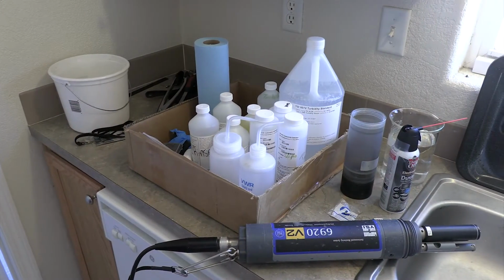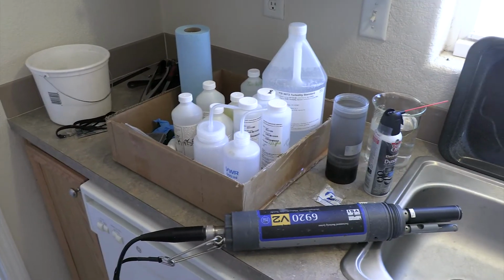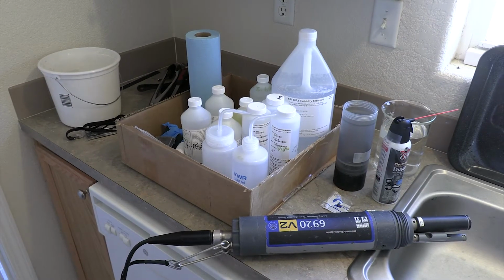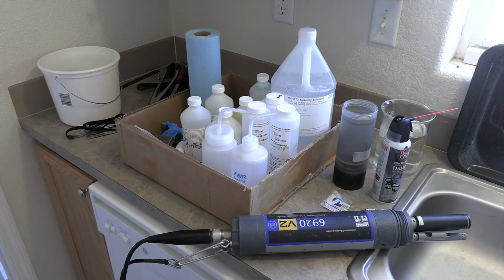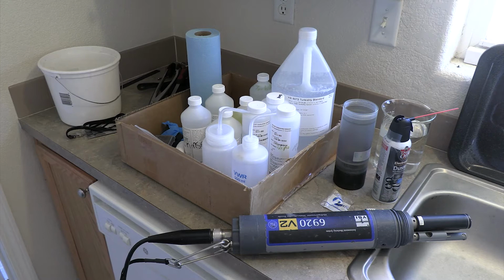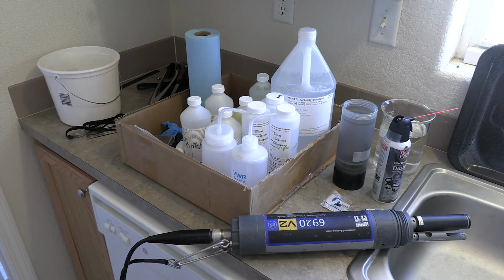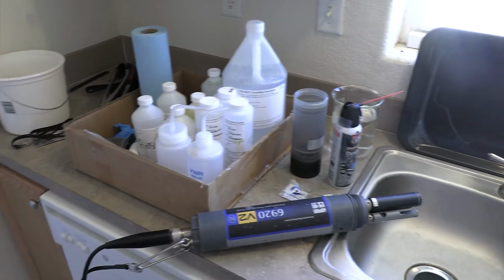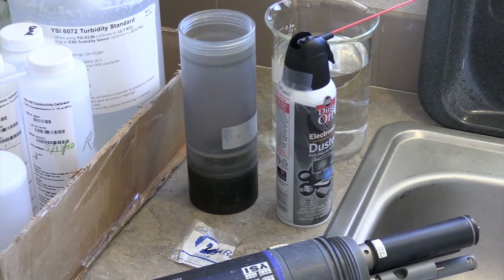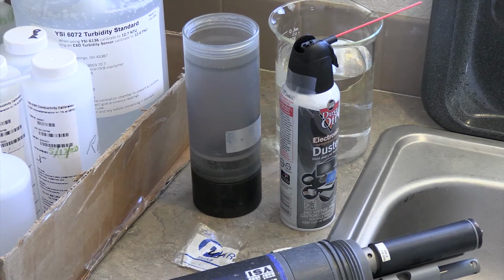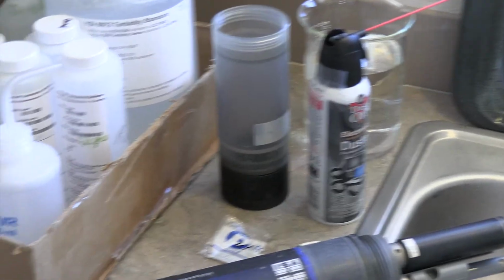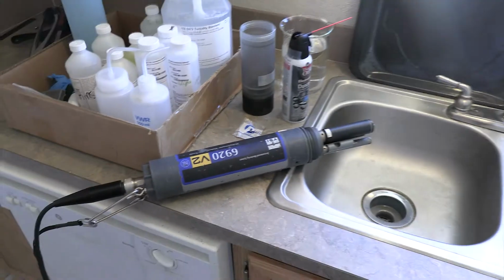Okay, so let's go over the rest of the equipment here, the important stuff. In front of me is all the solutions that we use to calibrate. We have some cleaning solutions, and then all the actual solutions, and then rinse solutions, so we can use the spent solutions to rinse out the calibration cup. To the right of that we have our calibration cup, and then we have air to blow out the joints and clean out some of the ports, and DI water behind the air, and then we have our 6920 probe.